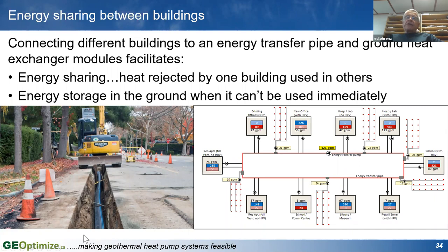Colorado Mesa University has done that for a couple of years. They started building their system about 8 or 9 or 10 years ago. Missouri State University of Science and Technology has a system somewhat similar to that. So there are systems there. You're starting to see systems that are being developed as district energy systems. There's heat pumps in each building, and they just simply draw heat from this pipe or dump heat into that pipe. And if you've got a fairly diverse mix of buildings, that can be really, really beneficial. If all the buildings are the same, the heating and cooling load profiles are going to be the same. But if you've got some diverse loads, and university campuses are really good for that simply because they've typically got residence buildings, classroom buildings, office buildings, they all operate differently.